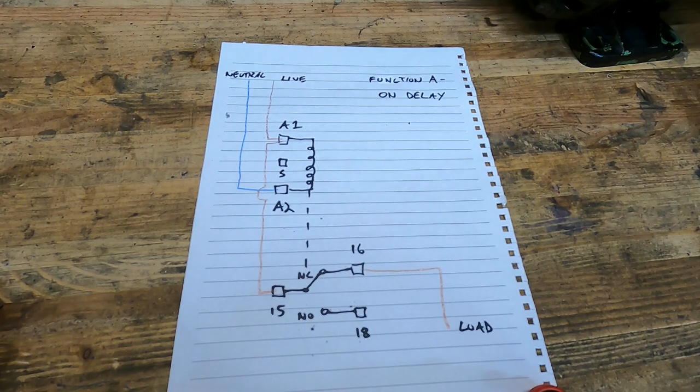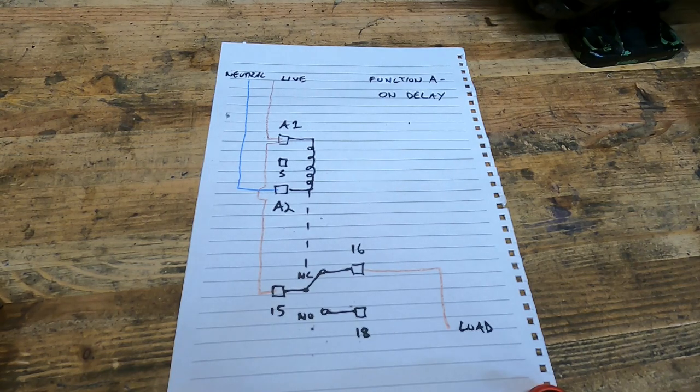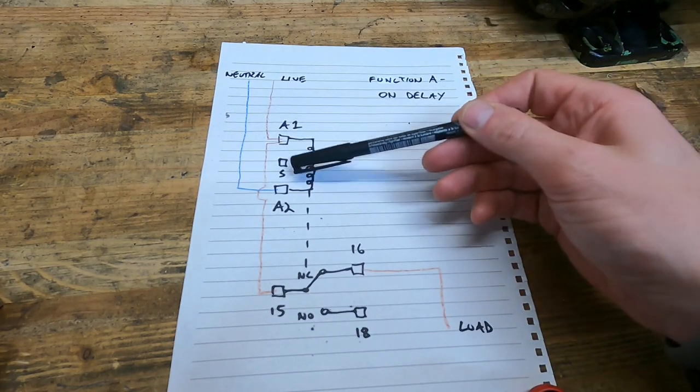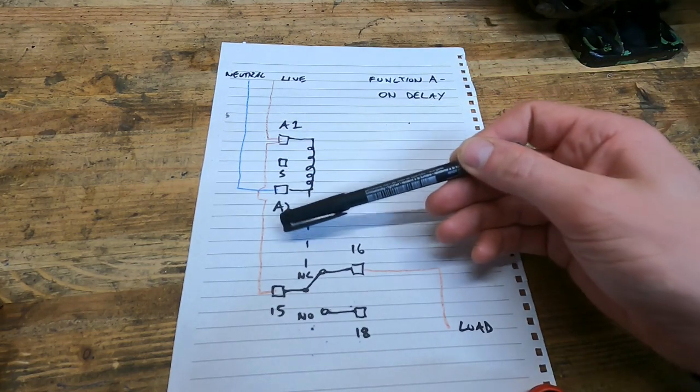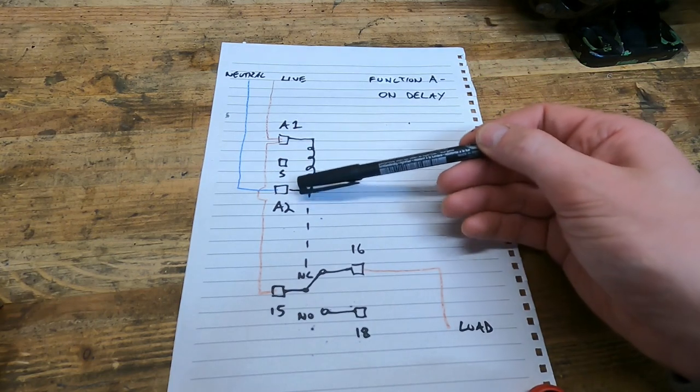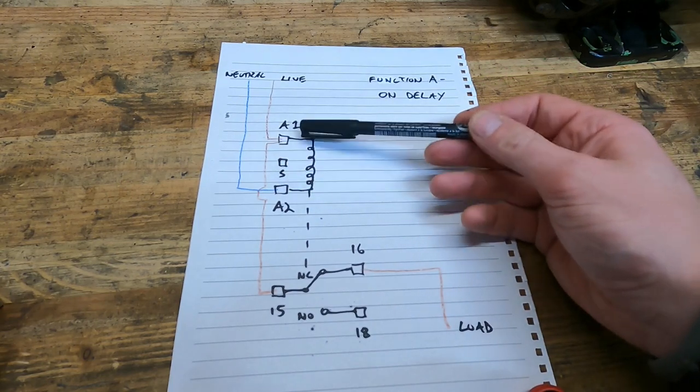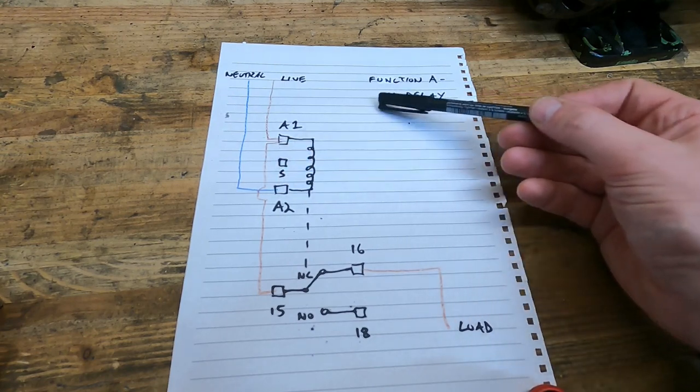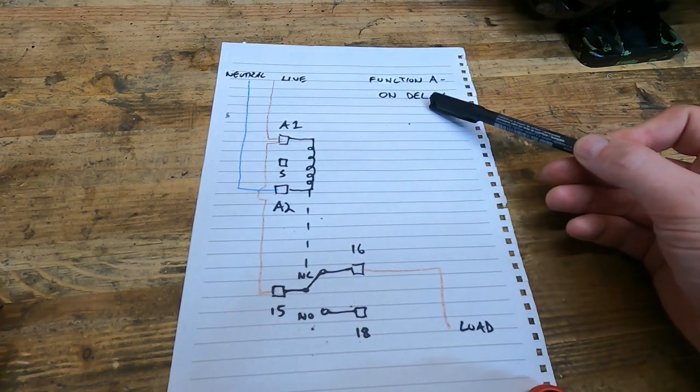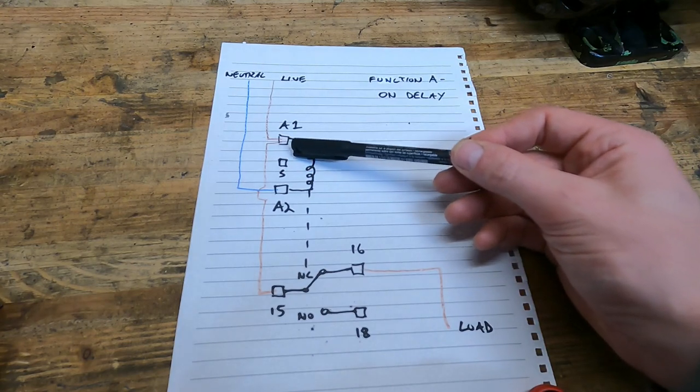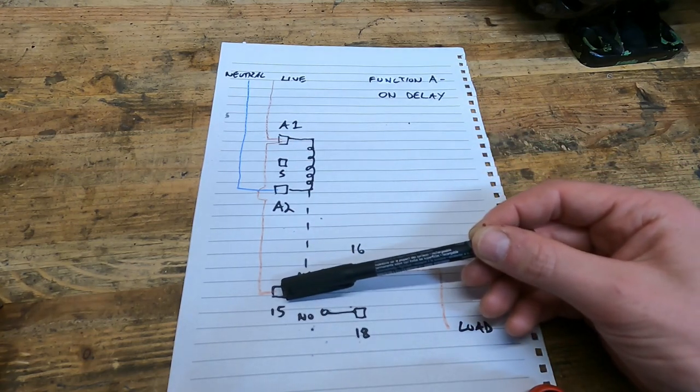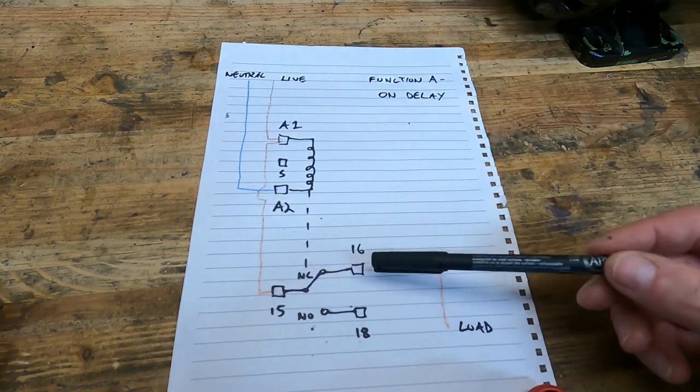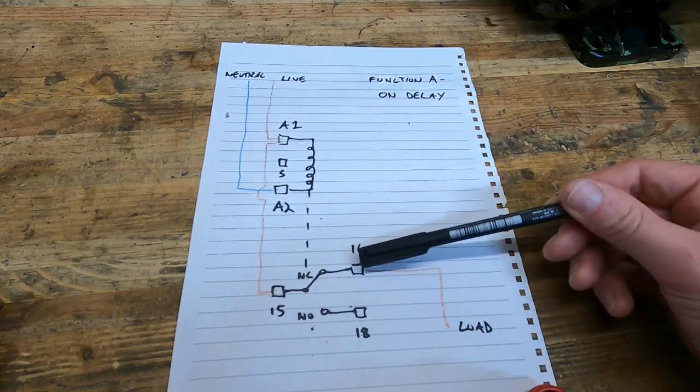I thought it'd be worth spending a minute explaining how this time delay relay works. So we have four terminals on the input side: A1, S, A2, and 15. A1 and A2 are the live and neutral for the coil. S is a trigger switch which we don't need with the function that we're going to be using—function A on delay. Terminal 15 needs a live feed from A1.